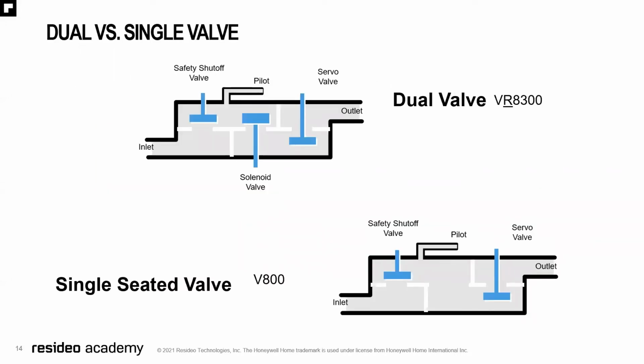Dual versus single valves. Modern valves, dual valves, will have a safety shutoff, a solenoid valve, and a servo outlet, making it a dual valve. And we have single-seated valves, typically only found in millivolt at this point, where you only have a safety shutoff and then just a servo valve for the main burner.